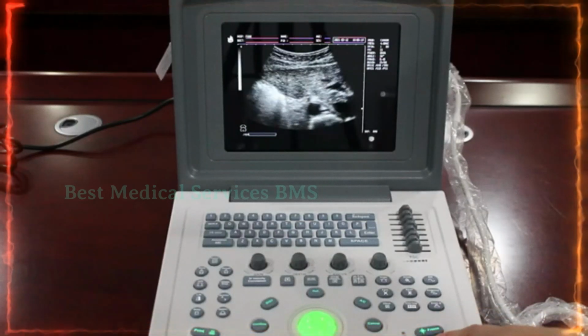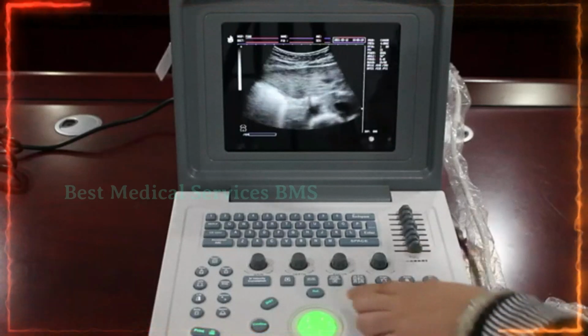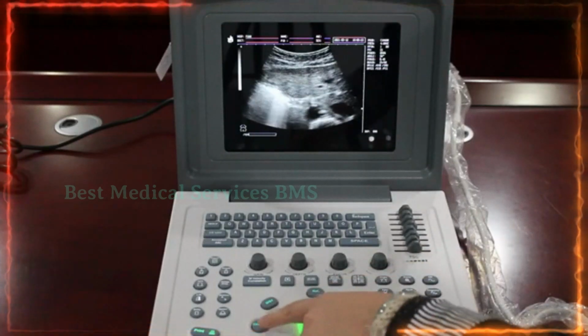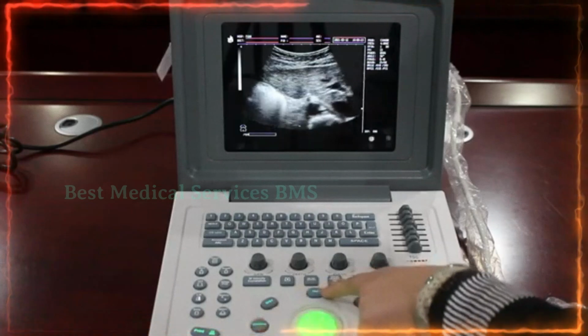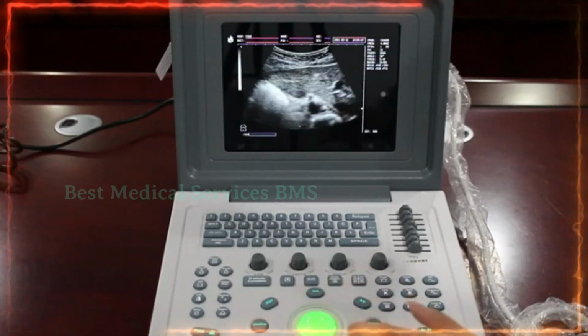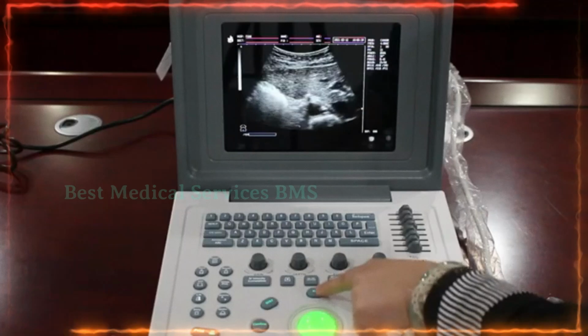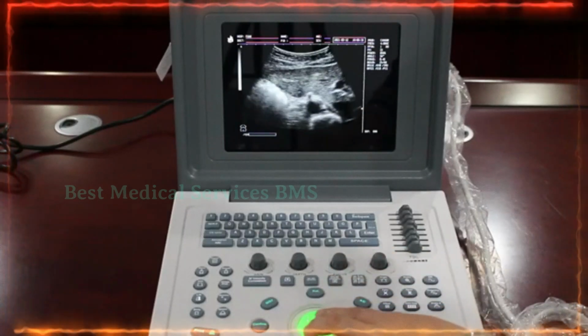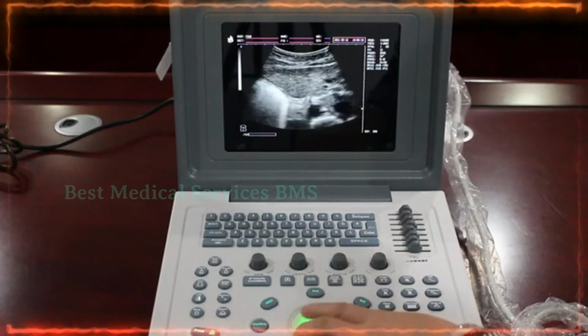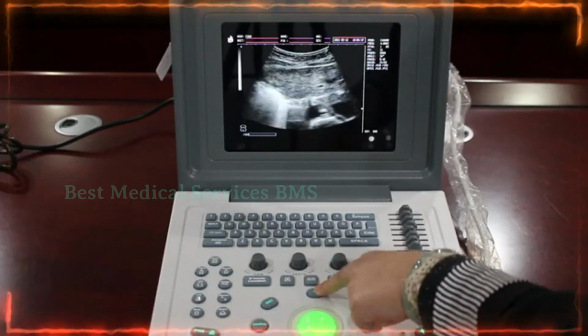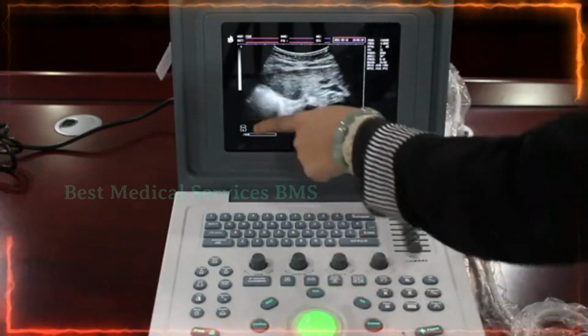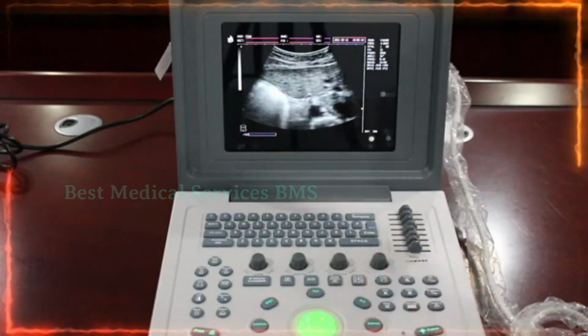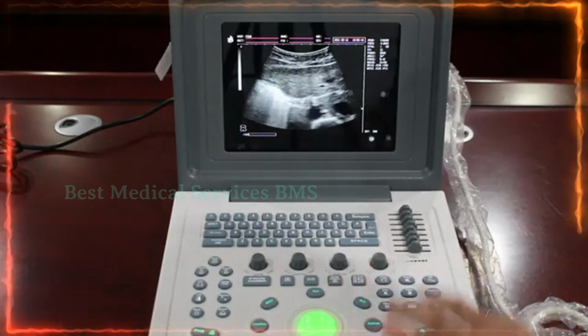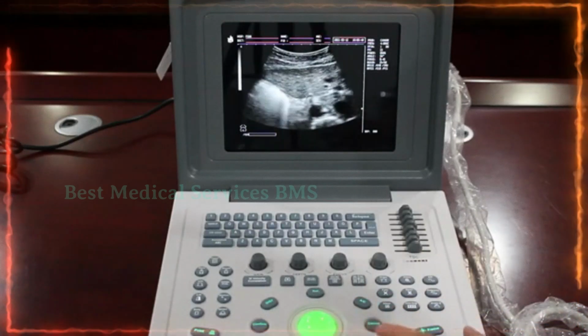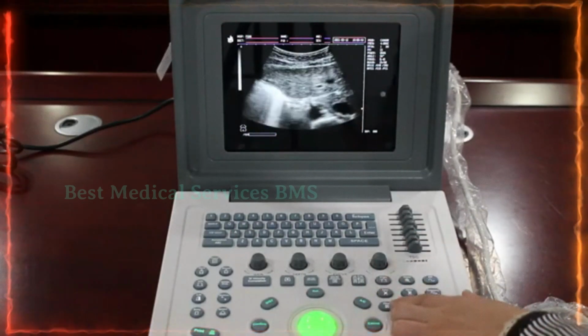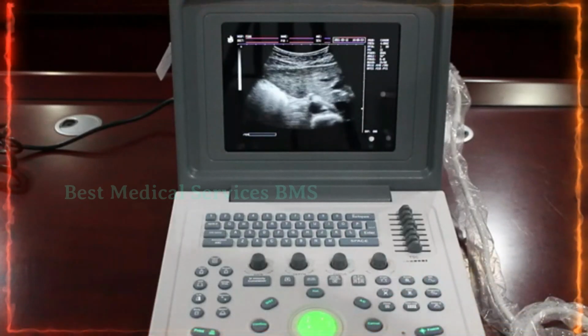Press freeze again to unfreeze the image, and you press confirm, and we can add the indicator with directions. Press before, then you can see the indicators. Before it, the direction of the indicator is changed. If you don't need the body marks, we can press the clear button to remove it.